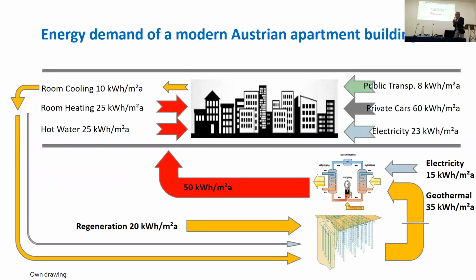How do we do it then? So this technology gives us very good options to have a balanced heating and cooling system. This is the heating demand situation of a modern apartment building in our climate. We design it with good heat insulation and get down to 25 kilowatt hours per square meter treated floor area without a ventilation system. If we apply this cross flow heat recovery ventilation system, we will get down to 15 or something. Hot water is still the big issue.